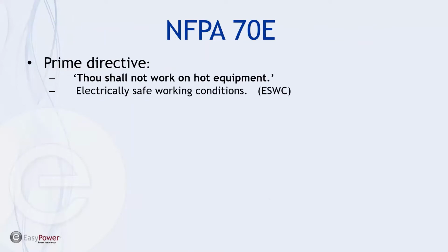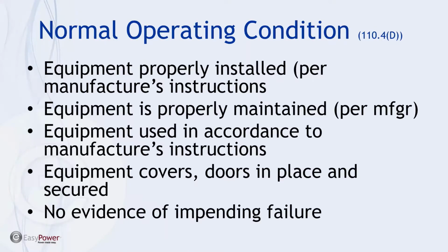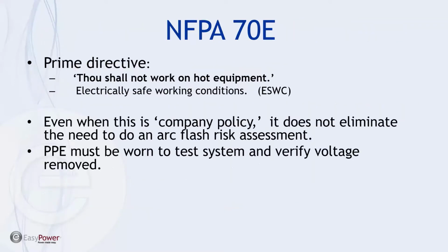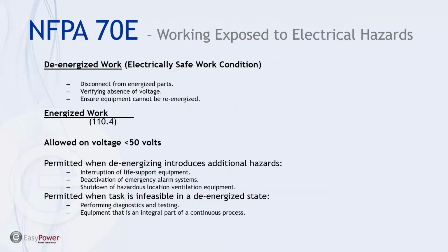And this goes back to the operating conditions. If one of the requirements for equipment manufacturing maintenance is to be able to inspect, adjust, or otherwise test equipment that's energized, we can't very well do that de-energized. And so that exception is referred to as infeasible. And each of these electrified conditions, the two categories where we could do electrified work, needs to be done under the auspices of a hot energized work permit.